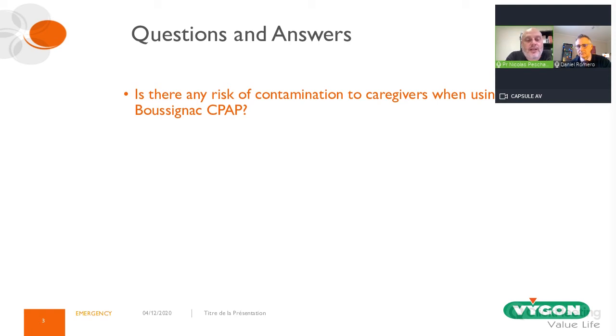But very quickly, with Georges Boussignac himself, we tested different kinds of filters. First, to protect the healthcare providers, of course, but also to see if the flow stayed the same, because as I said, it's a virtual valve that needs a certain amount of oxygen, and we wanted to check if the device still worked with the same mechanism. So there is a very tiny decrease of the flow, but it's not clinically relevant. So it was very reassuring for us that the flow and the mechanism itself stayed the same. So you have to use a HEPA filter to protect your healthcare providers, and you can use it without any decrease in the efficacy of the system.